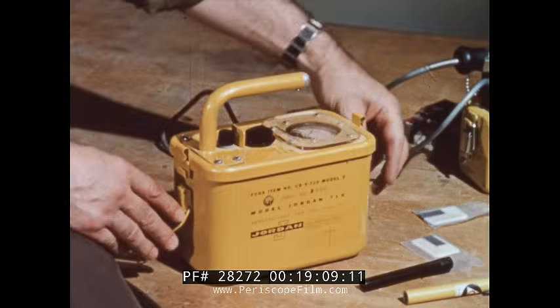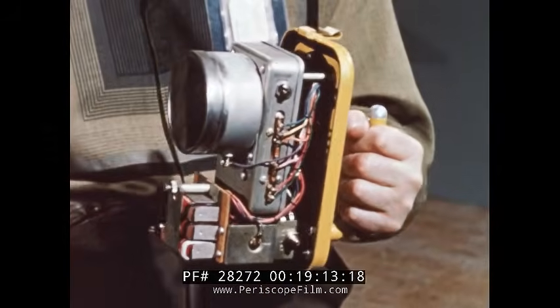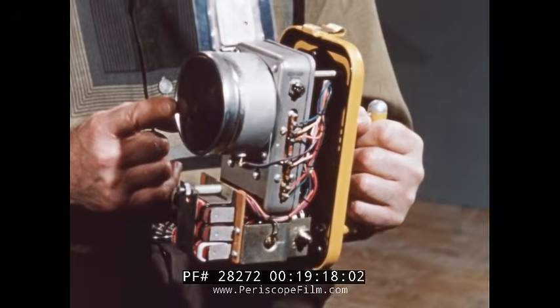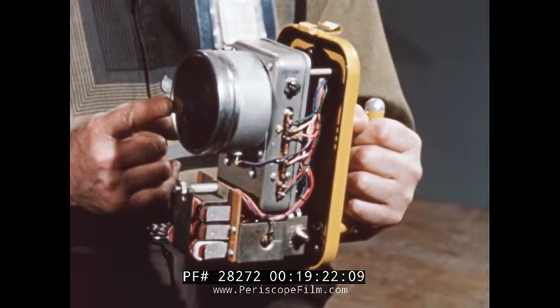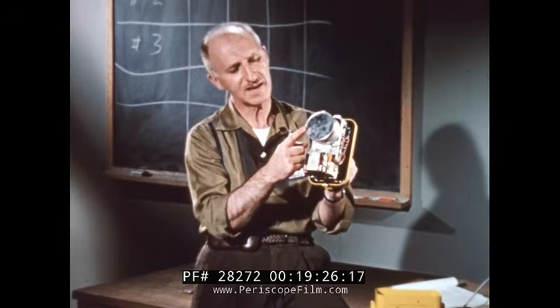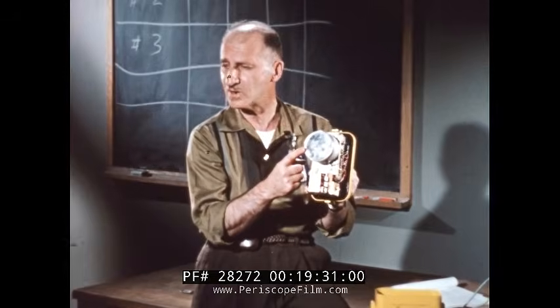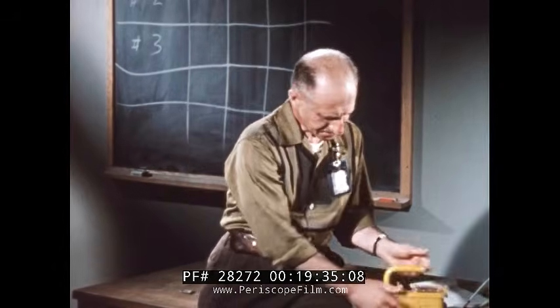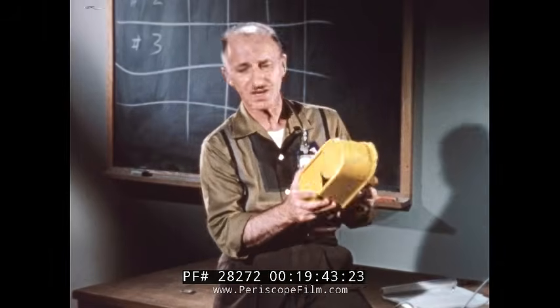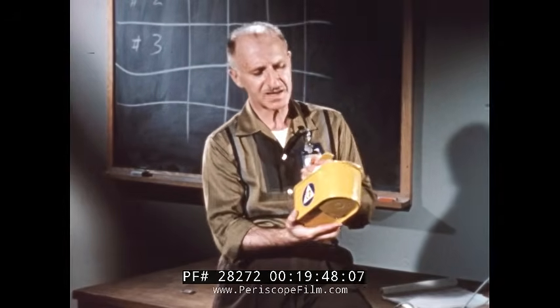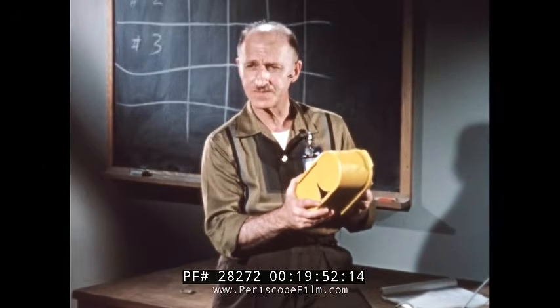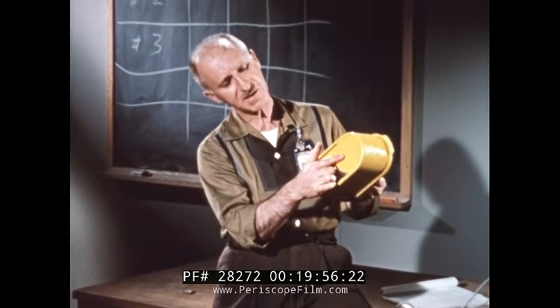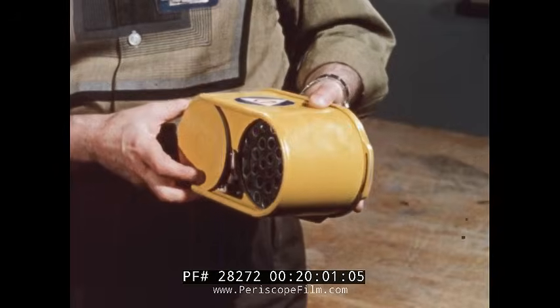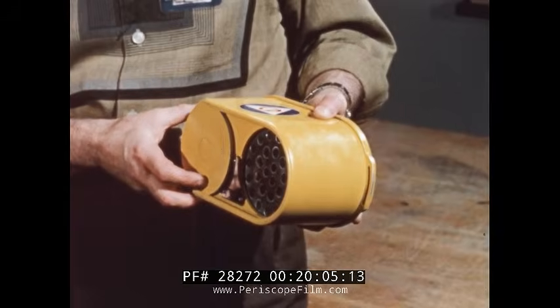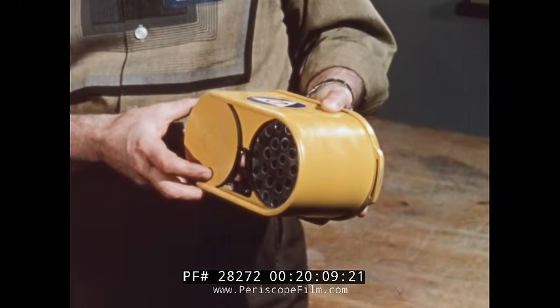Inside, the 710 is much like the 700, with the addition, of course, of the ionization chamber. This chamber is hermetically sealed to minimize the effects of temperature and to eliminate altitude and moisture factors. The 710 will be the workhorse in any attack situation. The other instrument we have here today is the CDV 720. And although we won't be using it in our exercises, it might be well to say a few words about it. It, too, is an ionization chamber instrument, but unlike the 710, can measure beta radiation. The beta shield is located on the bottom of the instrument, and when opened, exposes the beta window in the chamber. The 720 is a high-range instrument and can measure up to 500 R per hour.